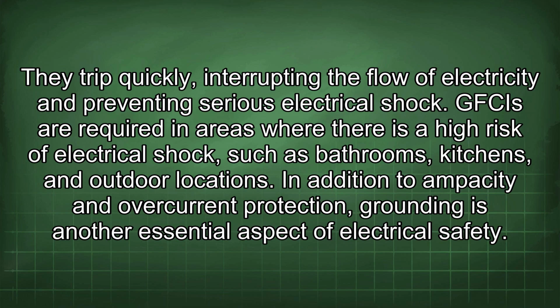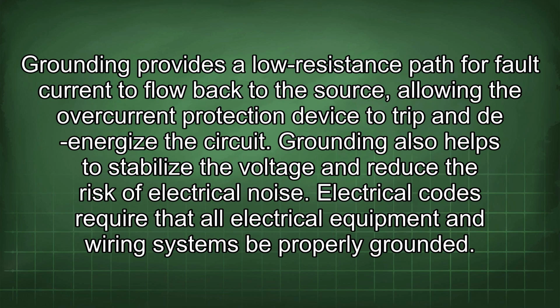In addition to ampacity and overcurrent protection, grounding is another essential aspect of electrical safety. Grounding provides a low-resistance path for fault current to flow back to the source, allowing the overcurrent protection device to trip and de-energize the circuit. Grounding also helps to stabilize the voltage and reduce the risk of electrical noise.